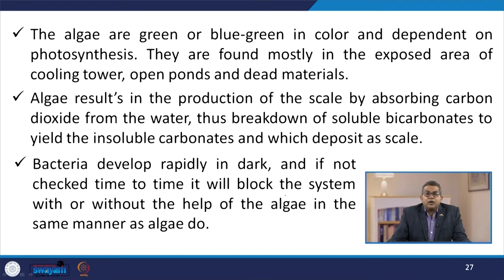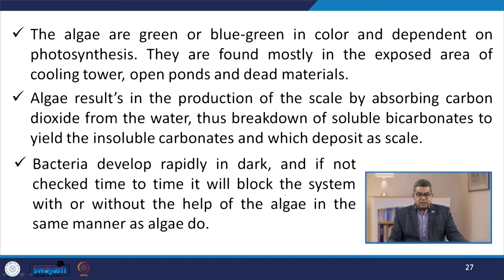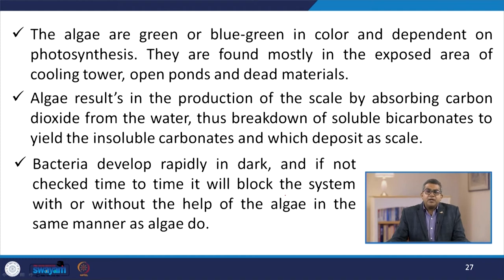Algae are green or blue-green in colour and dependent on photosynthesis. They are found mostly in the exposed areas of the cooling tower, open ponds, and dead materials. Algae result in the production of scale by absorbing carbon dioxide from the water, causing breakdown of soluble bicarbonates to yield insoluble carbonates, which deposit as scale. Bacteria develop rapidly in dark conditions and, if not checked periodically, will block the system — with or without the help of algae.